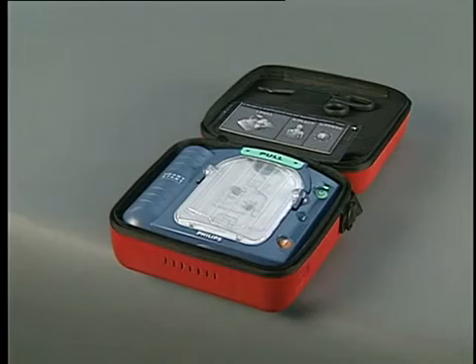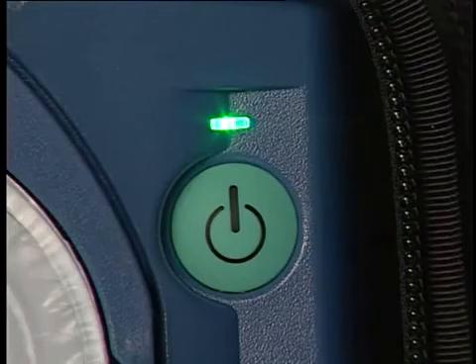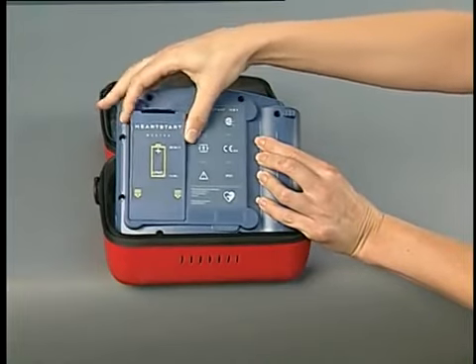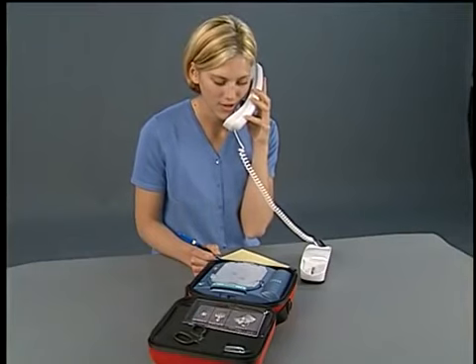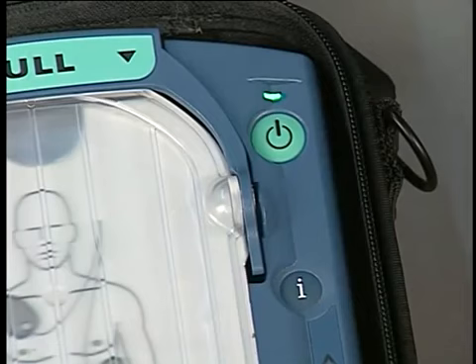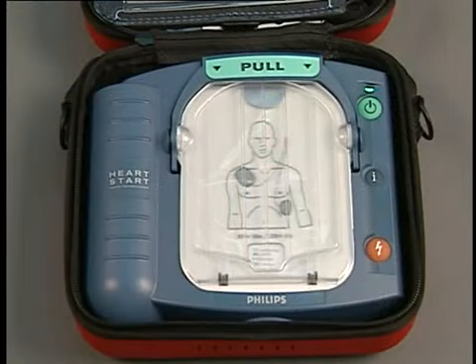If anything does not work as expected, make a note of the problem and contact Philips. When the interactive part of the self-test is complete, the defibrillator runs the automatic part, reports the test results, and then turns off. Check the ready light to be sure it is blinking. If the ready light is not blinking and the HeartStart is chirping, remove the battery for at least five seconds, then reinstall it and repeat the self-test. If a second self-test fails, contact Philips for service. In the unlikely event that the defibrillator is needed during the self-test, simply press the green on/off button or pull the pads cartridge handle to stop the test and turn on the device for use.